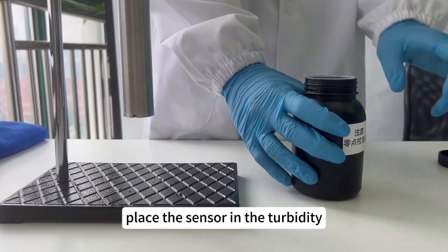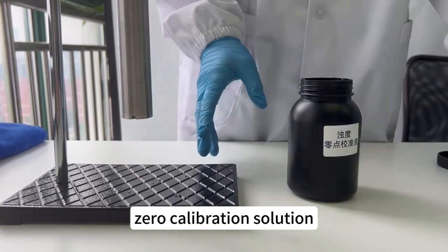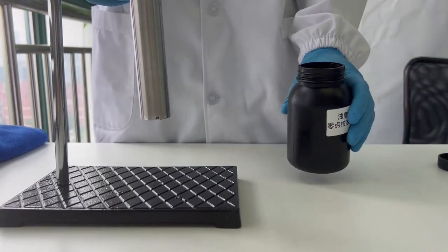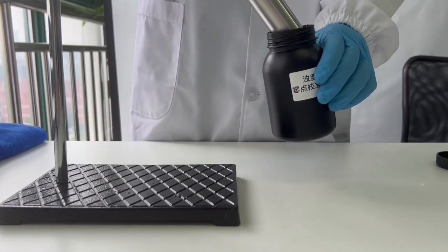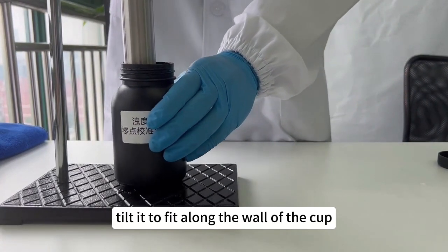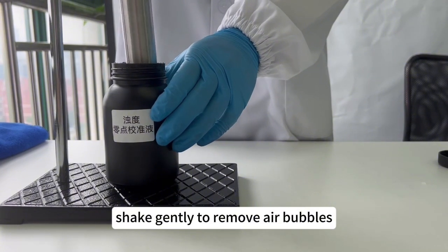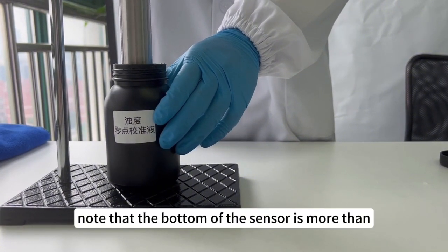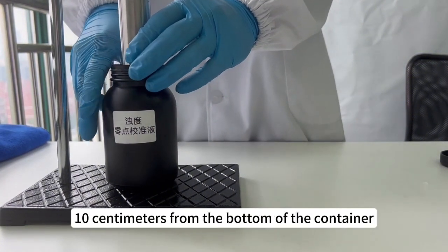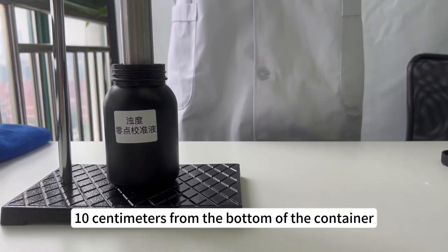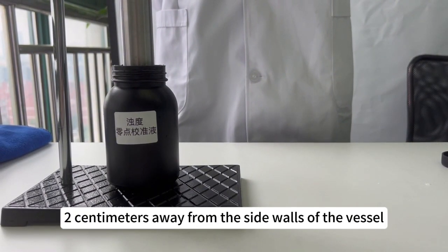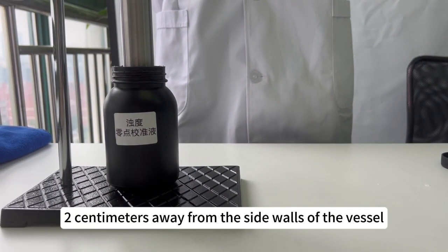Place the sensor in the Turbidity Zero calibration solution. Tilt it to fit along the wall of the cup. Shake gently to remove air bubbles. Note that the bottom of the sensor is more than 10 centimeters from the bottom of the container. Place the sensor more than 2 centimeters away from the side walls of the vessel.